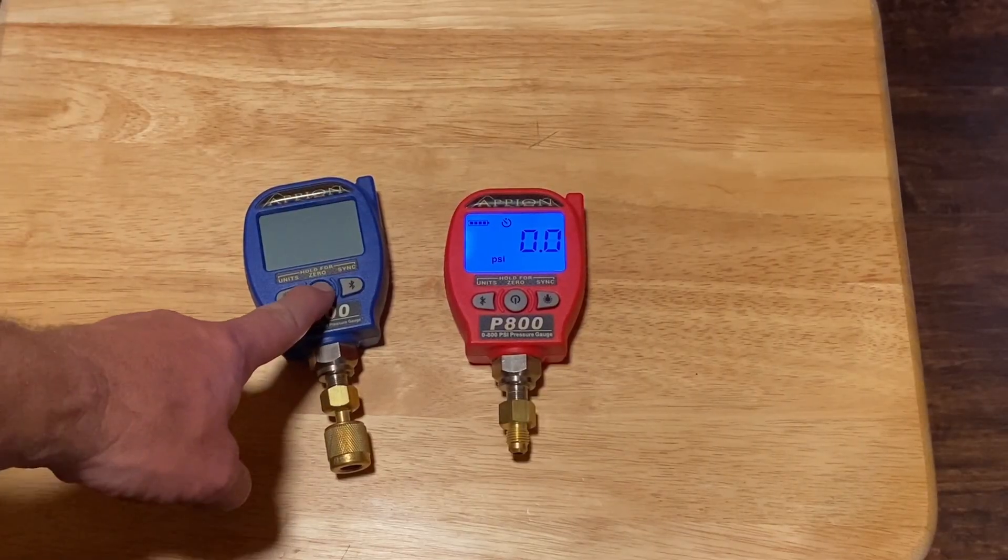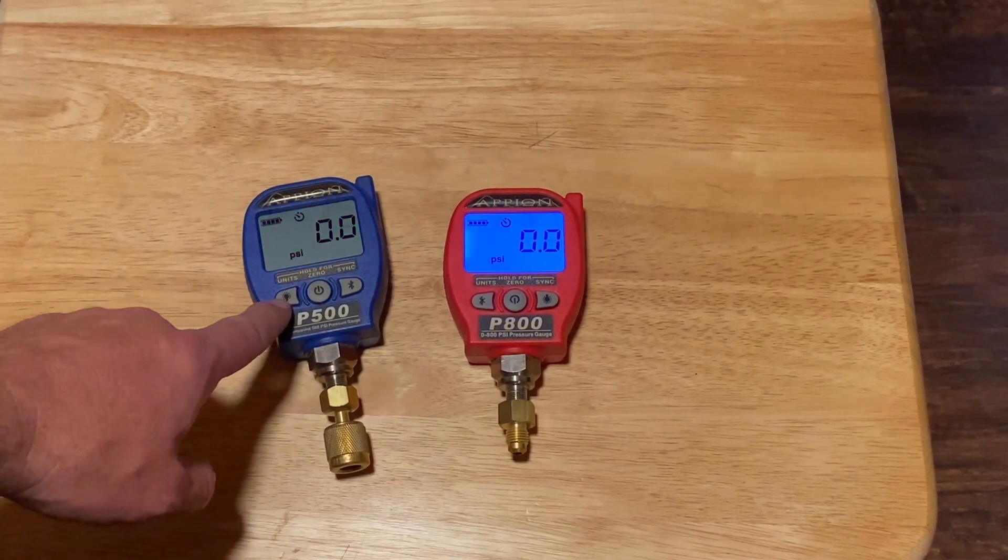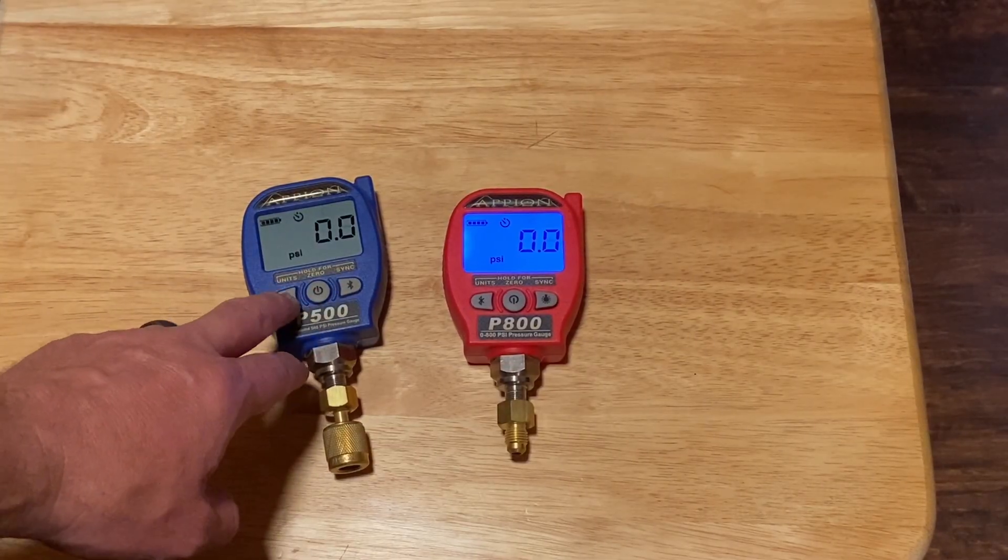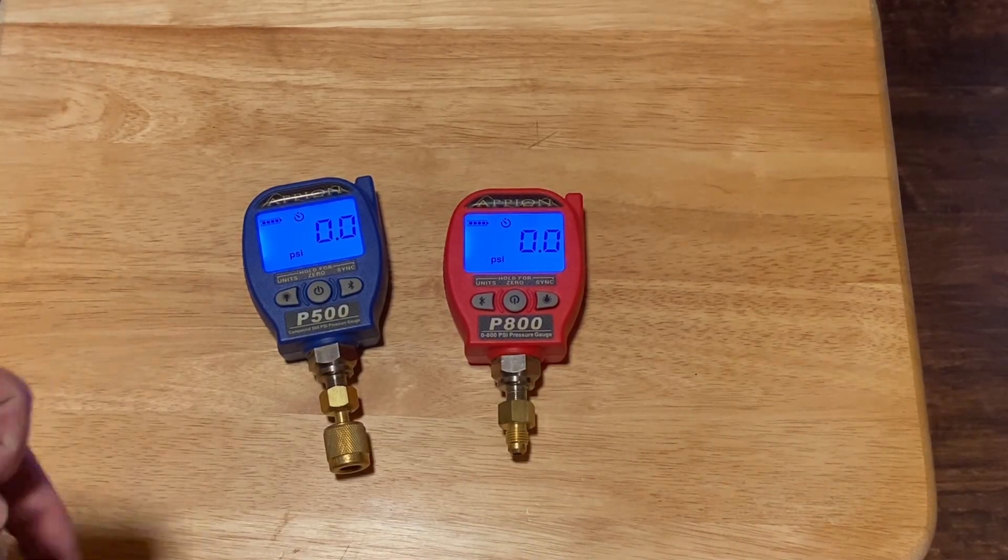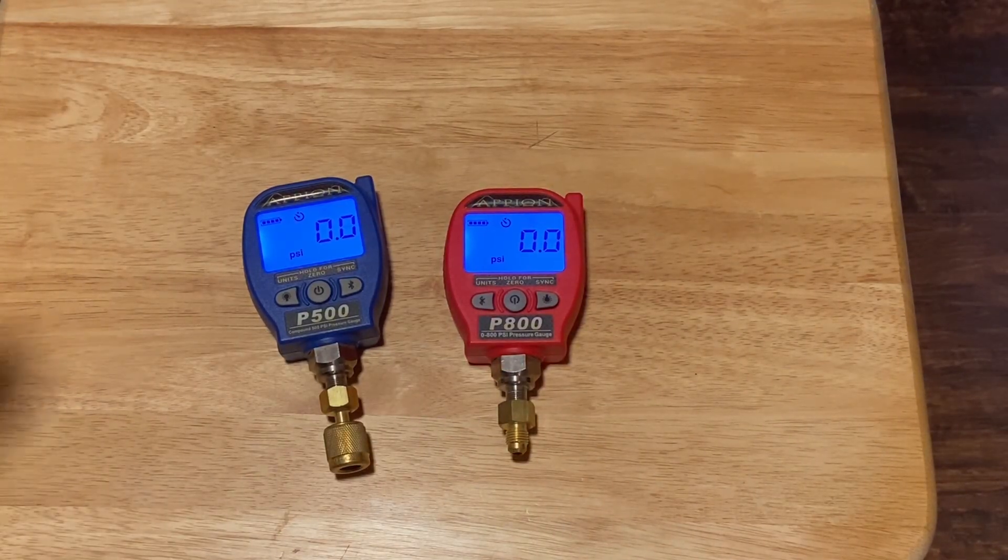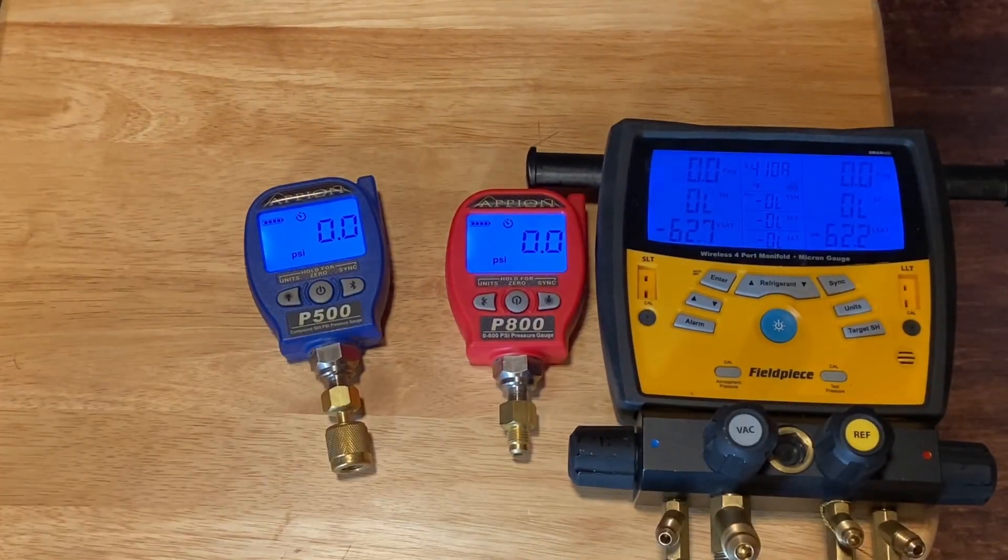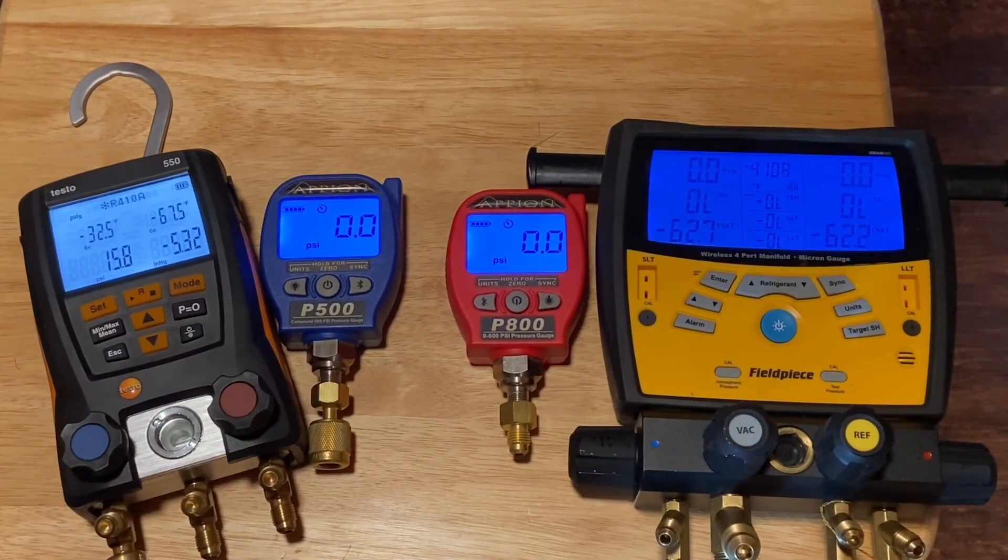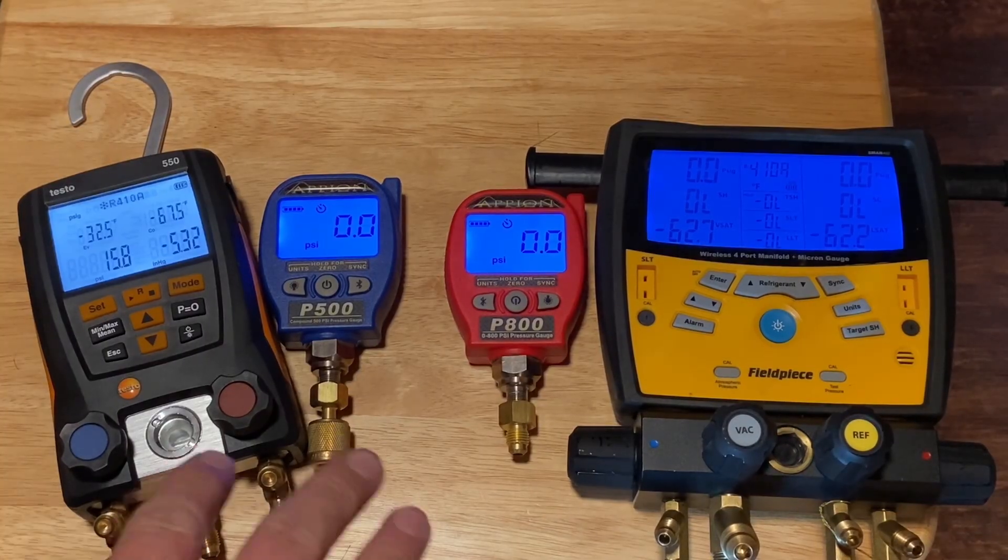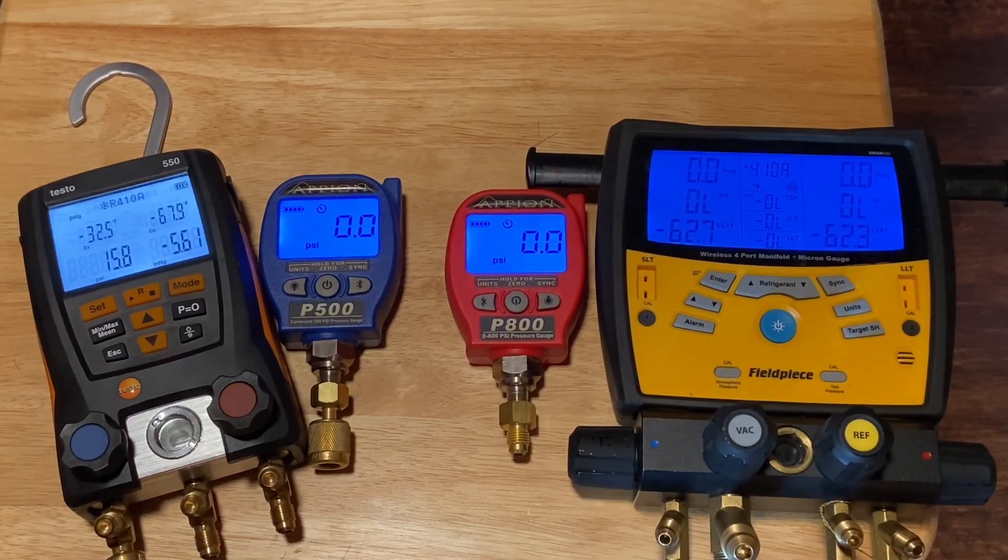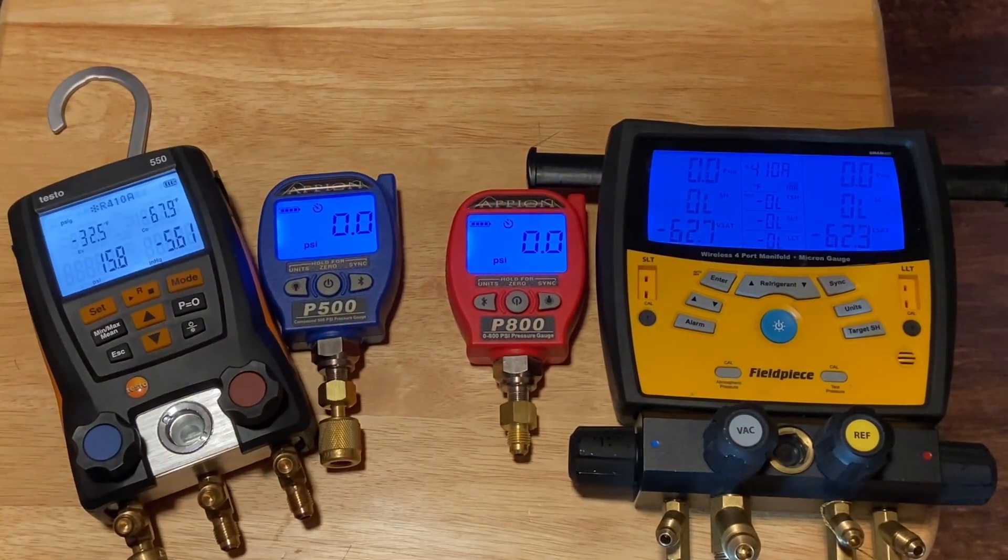We have another brand that is very similar. Here we have some other options. These are probes. These are really nice, because what I can do with these is I can put them directly onto a unit without having to have any hoses. There's less loss we have to deal with. And they have lights on them. This one also hooks Bluetooth. It'll hook to a Bluetooth to your phone. And with that, you can actually convert it to a saturated temperature on your temperature pressure chart from there. Many, many more different types. We're going to go through these and talk about the benefits and the downside of each one. But what is nice is with the digital equipment, it is much, much more accurate. It gives you a much more precise number. And as convenience goes, it gives you a temperature pressure chart built into the unit right there for you. So that's really, really nice. Accuracy is my main concern. Having that saturated temperature is also a benefit. And these things do much, much more on top of that. So eventually it's going to be your goal, but you still have to get past the EPA test and also understand a basic temperature pressure chart before you can really appreciate what these digital sets do.